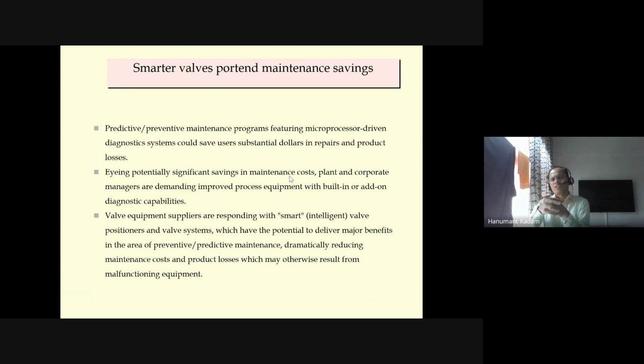So this, as I told earlier, a valve has no diagnostics available. Now, as I mentioned in the two or three slides, it acts as a controller. That way, it prevents damage and even predicts the degradation of the valve's mechanical parts, dramatically reducing the maintenance cost and product losses which may otherwise result from malfunctioning equipment. Suppose this was not available, the valve will remain as it is working, and one day it will stop. But if it is not controlling the required flow rate, then your product quality also suffers. That way, you are putting extra cost on your process, and at the same time you get a lower or a higher grade product, and that also costs the company.